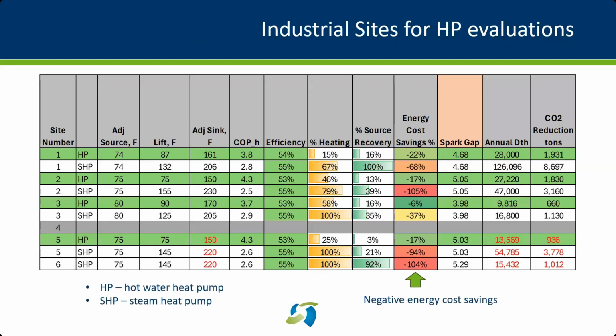And we did this for all 6 sites. For each of the sites, we looked at steam and hot water heat pumps. You can see that one of the sites did not have a steam heat pump possibility, but only had a hot water heat pump possibility. If I orient you to the table, the second column shows whether it's a hot water heat pump or a steam heat pump. It shows the temperatures and the lift needed, the COP for the heat pump, the efficiency compared to ideal efficiency for a heat pump, the amount of heating that can be provided, the amount of waste heat available that was recovered as a percentage, and the energy cost savings.